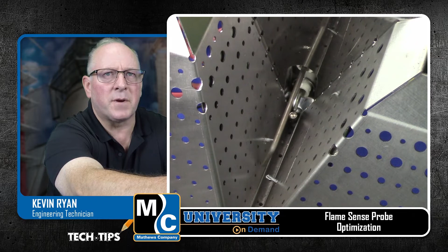Periodically when we're checking out a burner, we'll see something like this, and you can notice that the flame sense probe is actually hitting the side of the burner. If that condition exists, the burner will light momentarily and then go out, and it'll be very frustrating to find this.